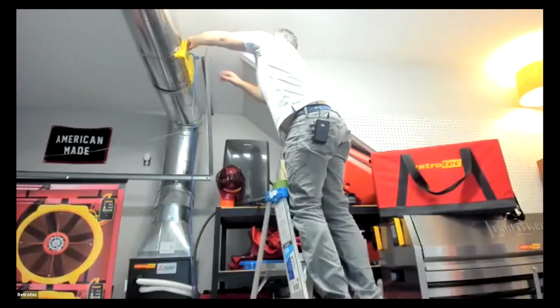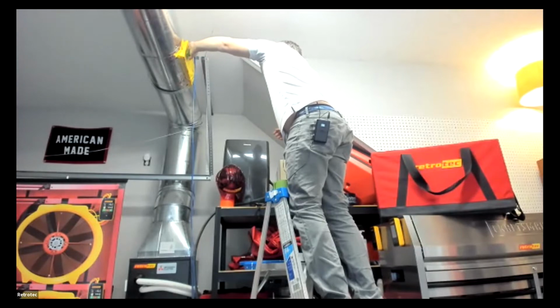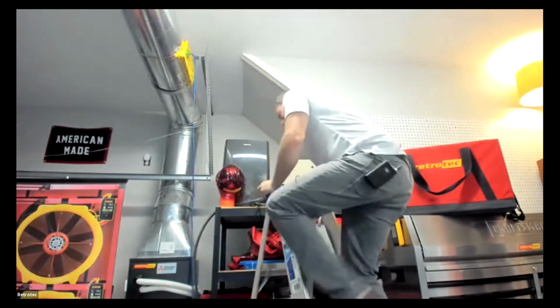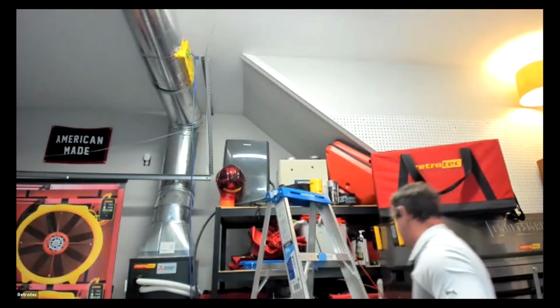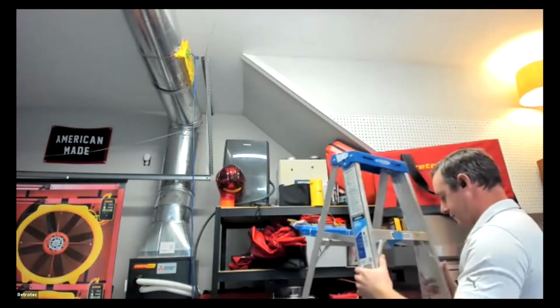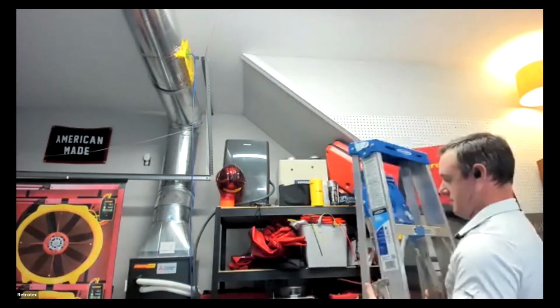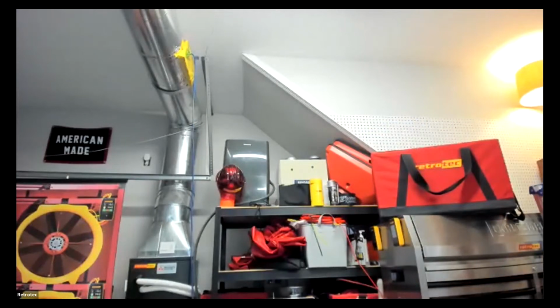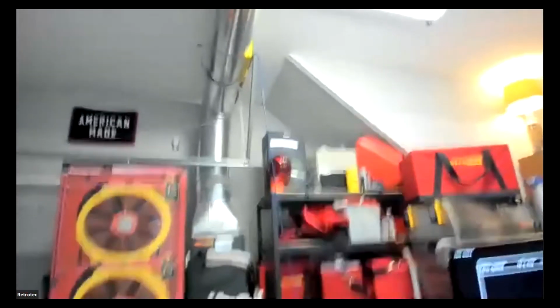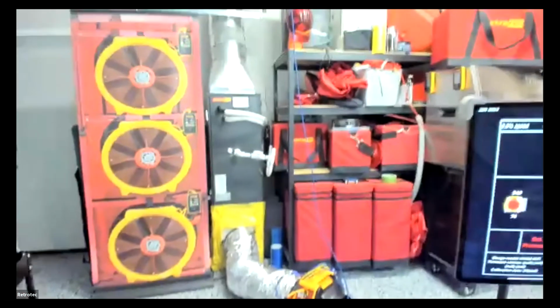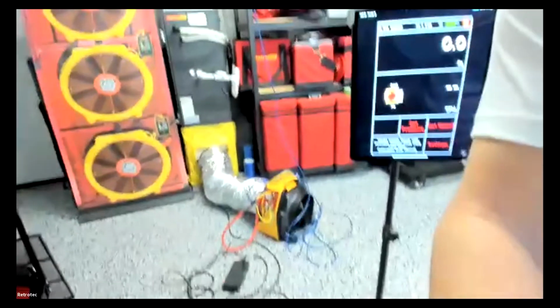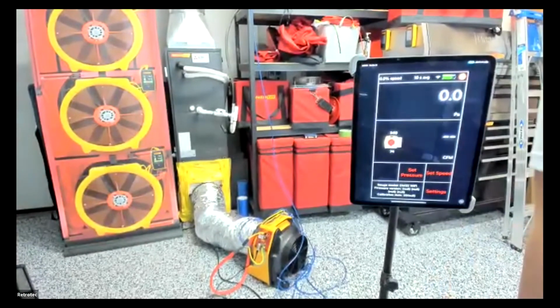I have done this before where it has fallen out, and I've run the fan and tried to figure out why I'm not getting the pressure. If you don't have anything in the duct system to read pressure, then the rest of it's not going to cooperate. So you want to make sure you have a good secure connection there. So now we're ready to run. We have everything installed. All of our tubing is hooked up. Our data cable is hooked up. Might be nice if I get you guys pointed back over so you can see. Let's get that iPad in there so you can see what's going on. Right on.